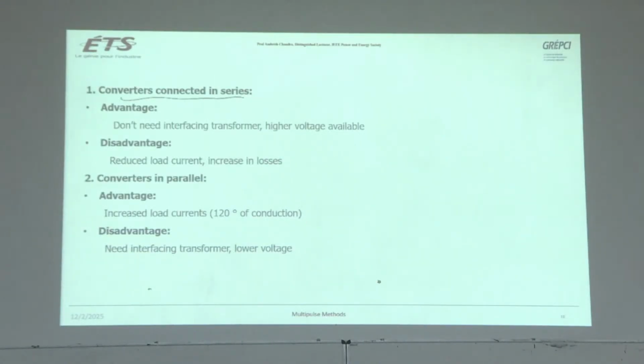If the converters are connected in series, there are certain advantages. You don't need an interphasing transformer if the converters are connected in series and you have higher voltage available. What are the disadvantages? Reduced load current, increase in losses. If the converters are connected in parallel, the advantage is increased load current. The disadvantage is that you need an interphasing transformer, and for parallel you have lower voltage.